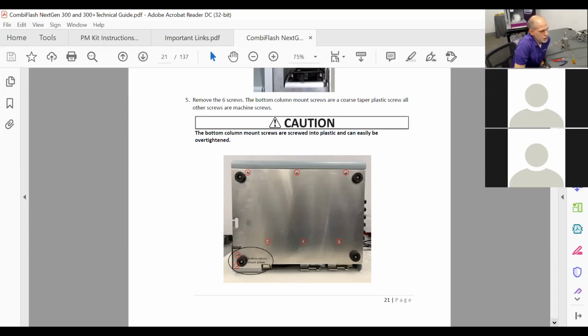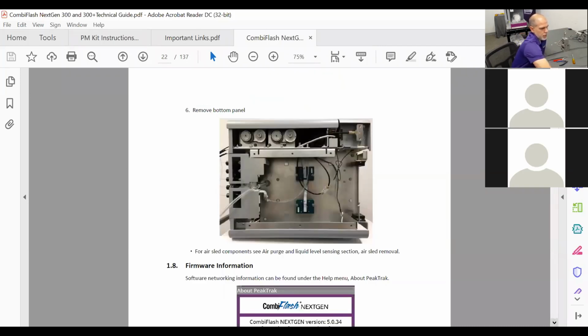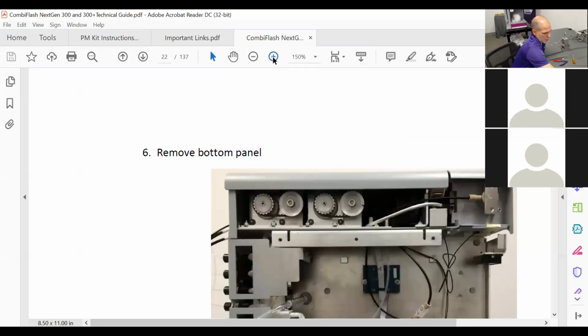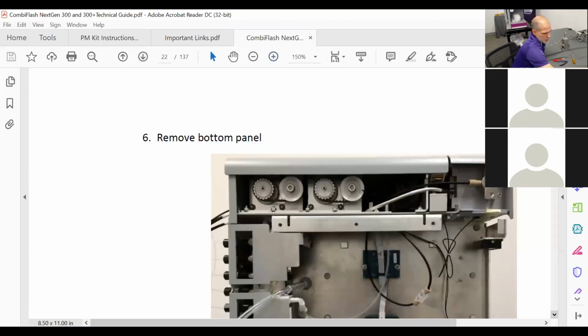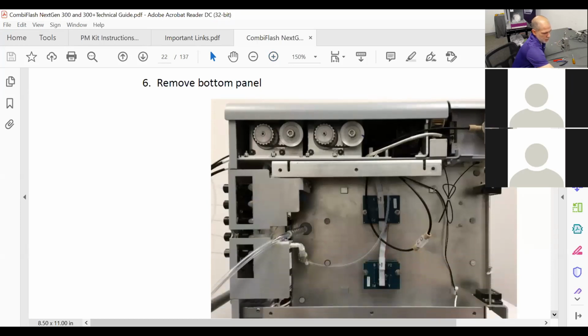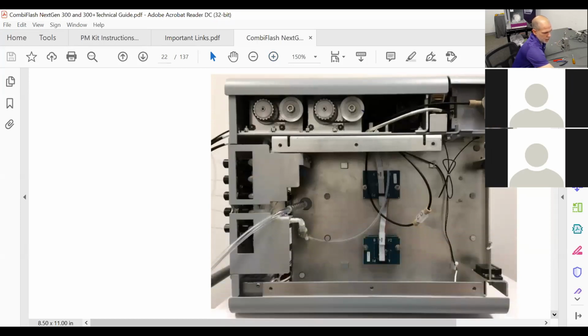Let's see here, but this picture shows where the screws are. You have to tip the unit on its side. We recommend tipping it on the side that the pumps are on. So that'd be the left-hand side. But it's pretty straightforward. And if you take it off, what you're going to see here is the bottom of the pumps. Here they tipped it over on the right side, and that's fine. I usually advise people do it on this side. But here's the bottom of the pumps.